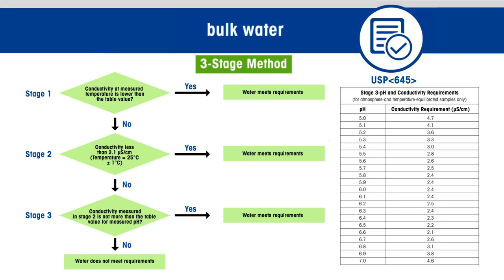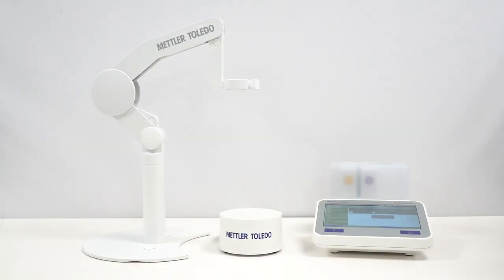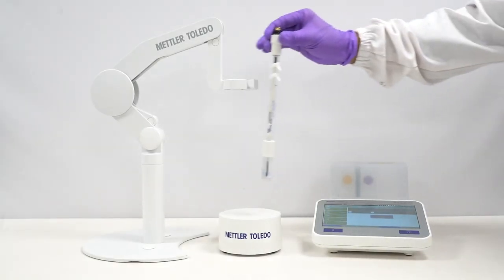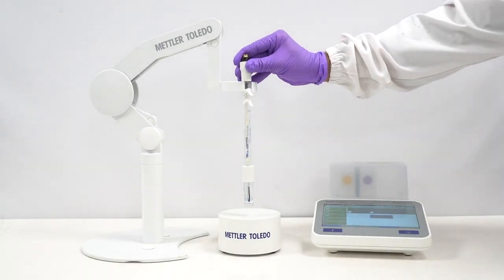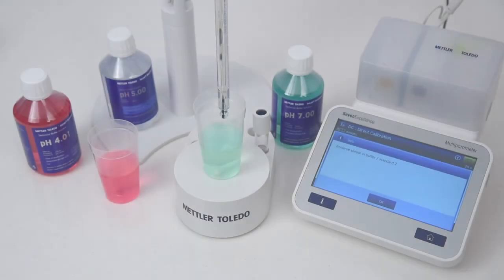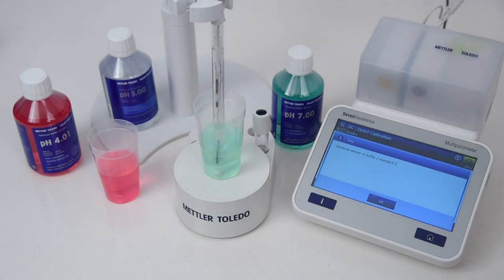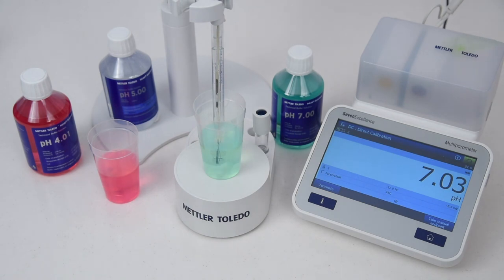For stage three, it is recommended to measure pH within five minutes of the conductivity determination of stage two. It involves the pH measurement of the sample and hence requires a pH meter and a pH electrode, adapted for samples presenting a low ionic strength. Calibrate the pH sensor according to USP 791.